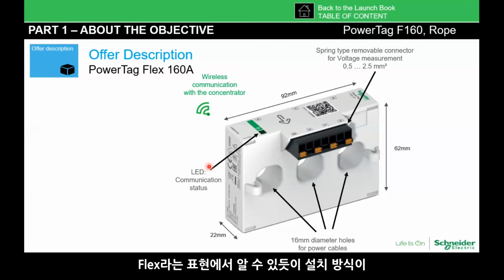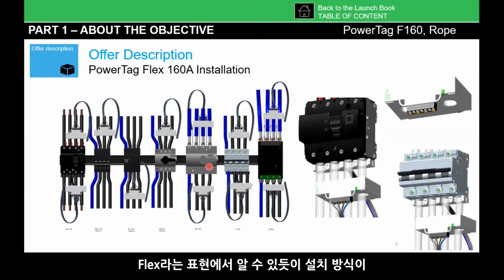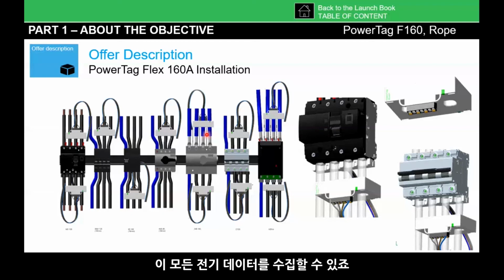And why we use the word flex is because of the way it's being installed—it's very flexible. We can use it on any brand of breakers in the market because you are just basically installing, hanging this CT here, and running the cable through the CTs. Then from the CT, you go by ZigBee communication to a gateway to collect all this electrical data. That's why we call it flex, because it's flexible in terms of installation.